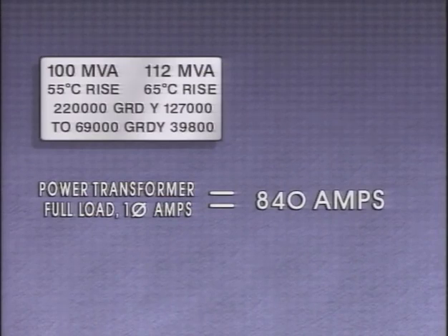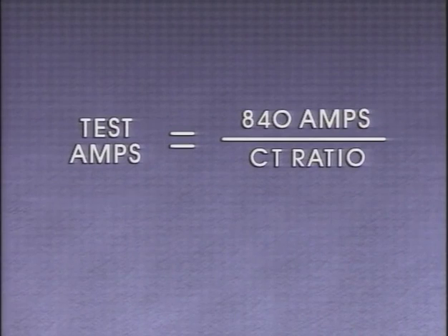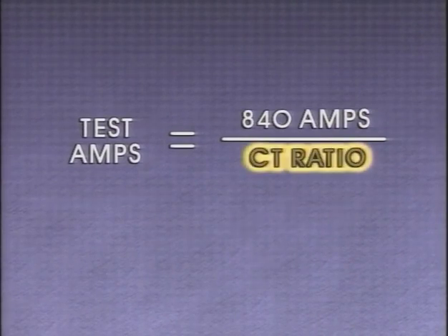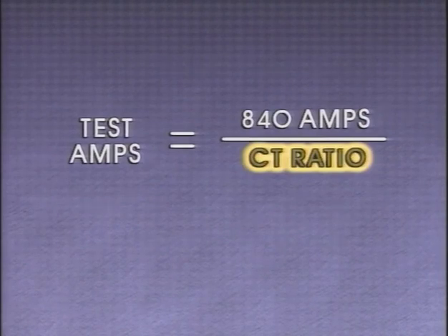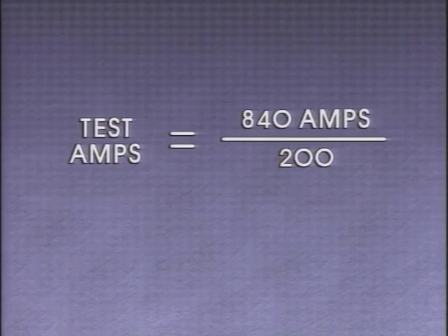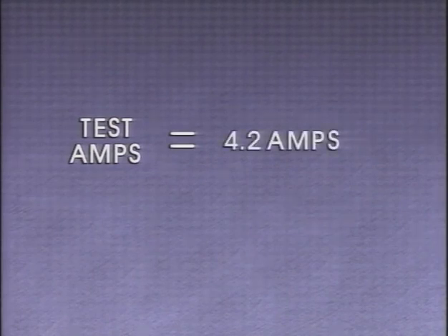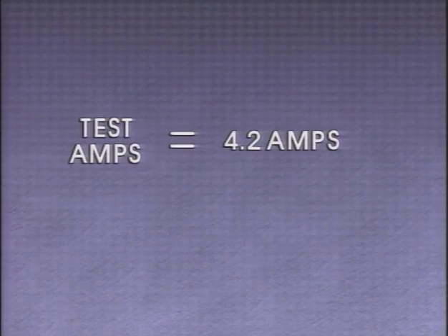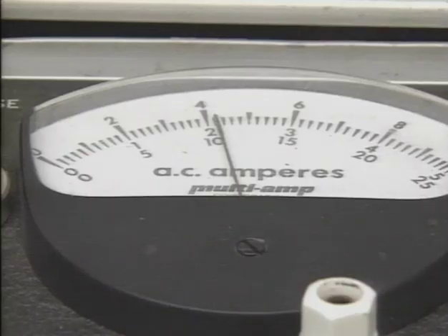Dividing 33,333 KVA by 39,838 V calculates out to about 840 amps, representing the primary current at the current transformer when the power transformer operates at full load. This figure is plugged into the test current formula: primary current divided by the current transformer ratio. The current transformer ratio in this example is 1000 to 5, or 200 to 1. Dividing 840 amps by 200 gives about 4.2 amps. The current transformer provides 4.2 amps to the winding temperature indicator heater circuit when the power transformer is at maximum rated volt-amperes, and 4.2 amps is the test current to be applied.